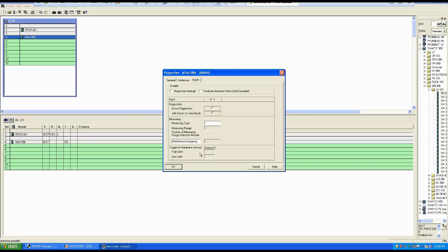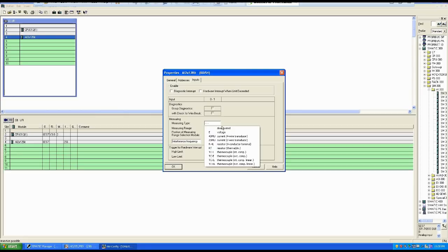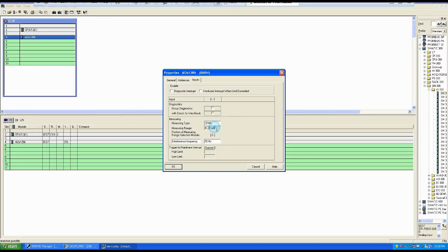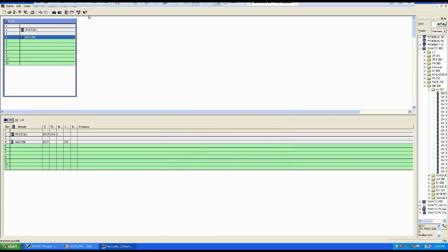Go to the input side and you will see different measuring types. Based on whatever type of instrument you are using, you select accordingly. If you are using an instrument with 0 to 10 volt you select voltage signal. For now I am taking current 2-wire signal which is 4 to 20 milliampere. I selected OK and it's now done.